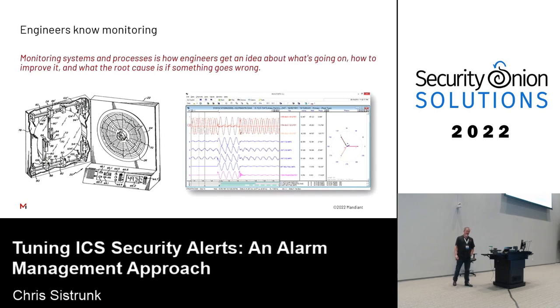On the left is what we call a wig-wag chart, a recording meter with a little pin that records something like volts or megawatts at a power substation over time—though it can also monitor temperature, pressure, anything like that. On the right is the A-phase power inside a relay during a fault on a transmission line. You can see the voltage collapse and the current increase for a few cycles, and the phasor diagram of what's going on.